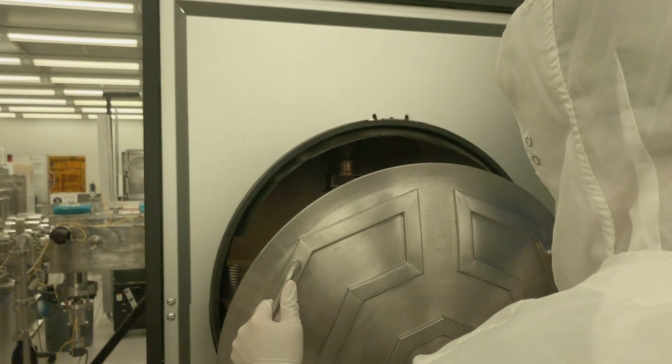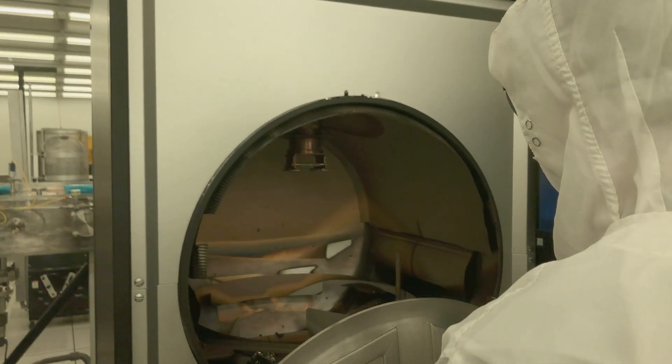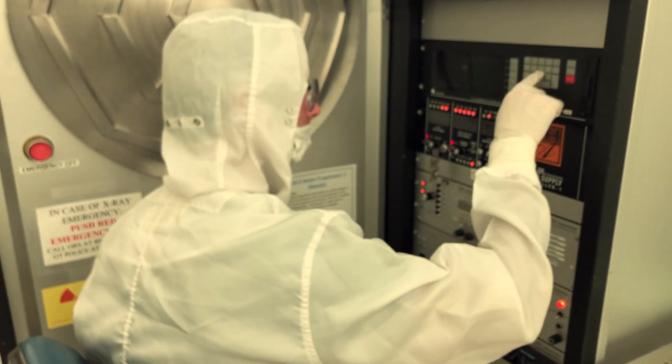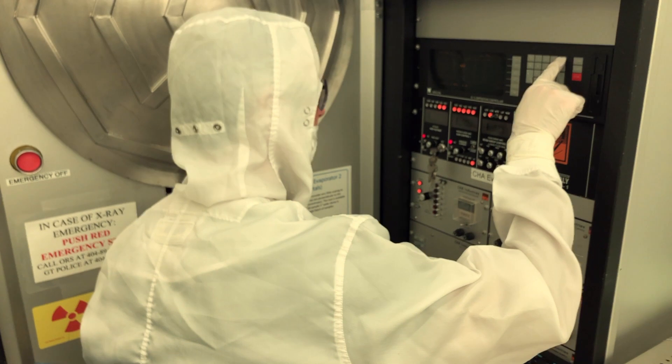The CHA Mark 40 Electron Beam Evaporator is used to coat samples with various metals. During a process, a high-intensity beam of electrons is focused on the center of a crucible containing a specified source metal. The energy from the electron beam causes the source metal to evaporate. The evaporated metal will then coat the surface of a sample with a thin layer.